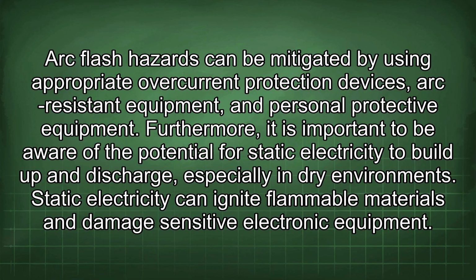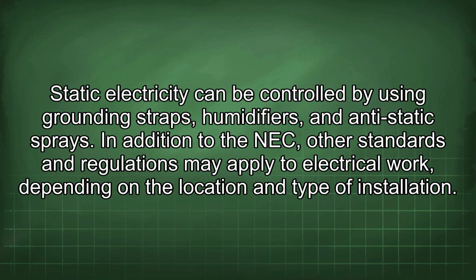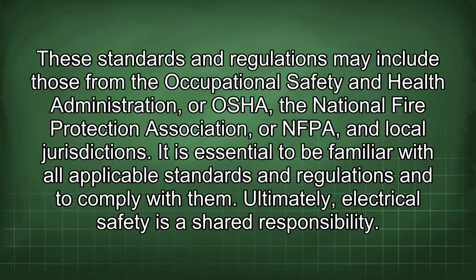Furthermore, it is important to be aware of the potential for static electricity to build up and discharge, especially in dry environments. Static electricity can ignite flammable materials and damage sensitive electronic equipment. Static electricity can be controlled by using grounding straps, humidifiers, and anti-static sprays. In addition to the NEC, other standards and regulations may apply to electrical work depending on the location and type of installation. These standards and regulations may include those from the Occupational Safety and Health Administration, or OSHA, the National Fire Protection Association, or NFPA, and local jurisdictions. It is essential to be familiar with all applicable standards and regulations and to comply with them.